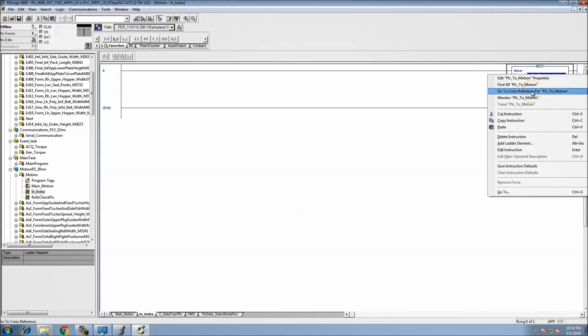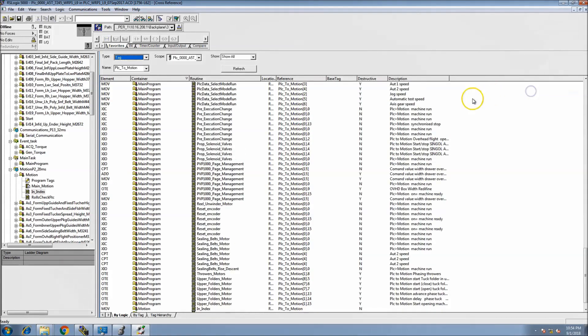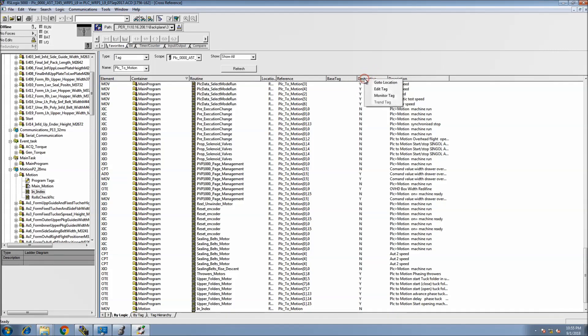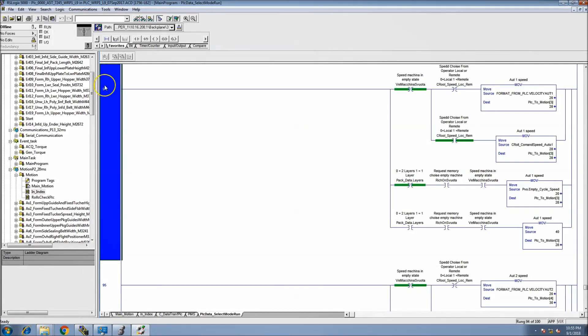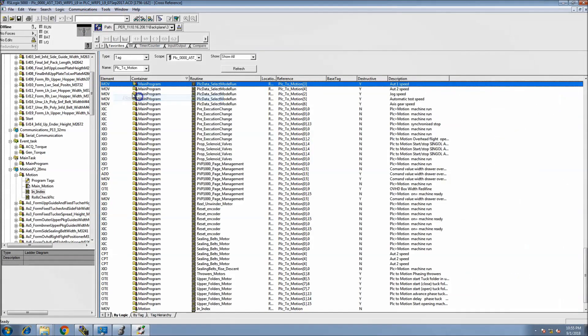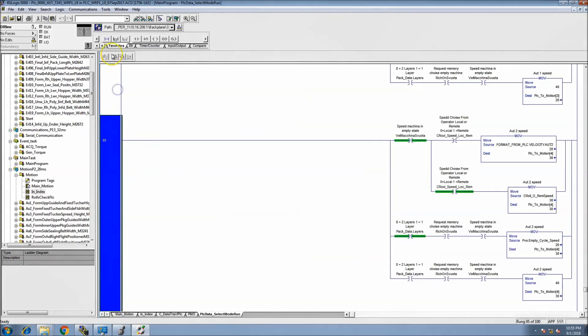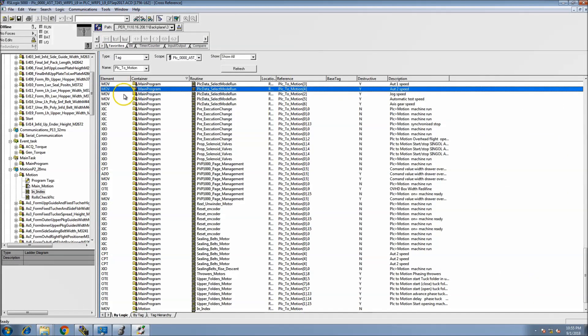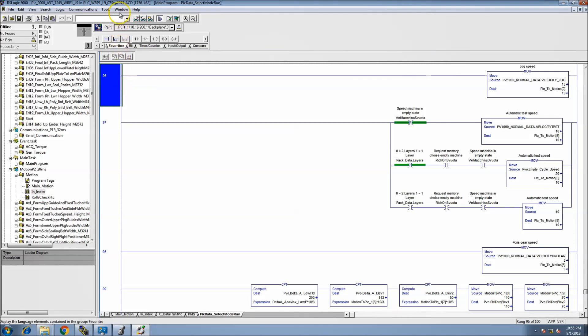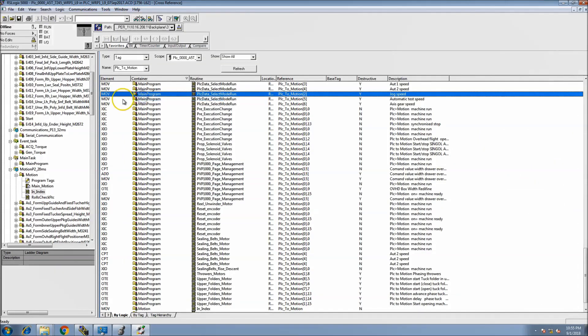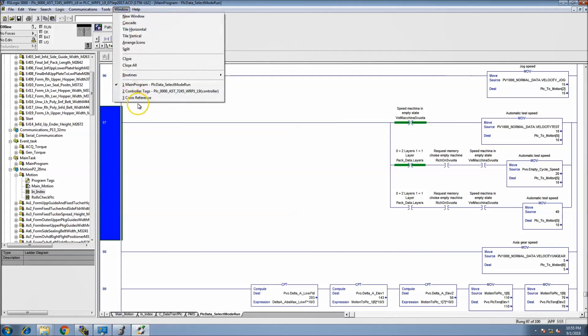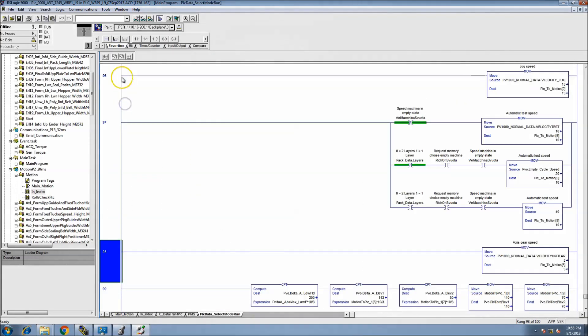Look at everything that's destructive and look for when an indirect addressing is being used. It's always going to be, I would say 99%, used in a move instruction. So you want to first look in destructive, basically look at all the destructives and compare. Every one that's a move, you need to check. So just go through one by one, I know it's a little monotonous, but go through one by one and check to see each one of them until you find your indirect addressing point.